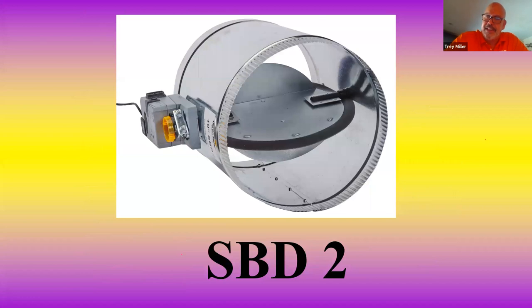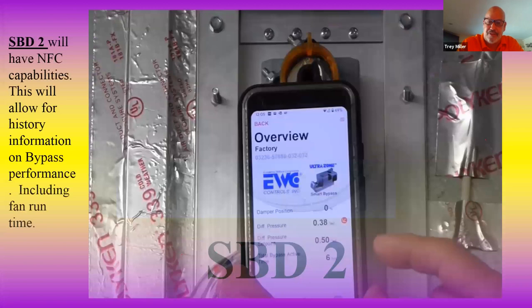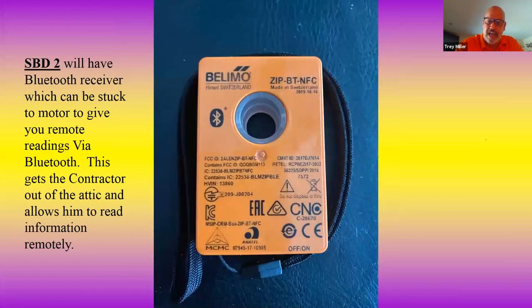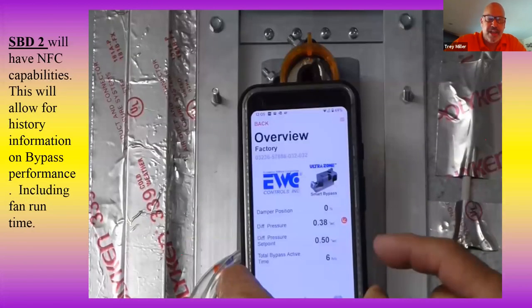Guys, this is exciting. John told me about this and I've been waiting, but the SBD2 is on its way. And let me show you what that is. First of all, you're going to have NFC, near field communication. The beauty of it there, guys, is you touch your phone to the motor, it's going to give you a readout, just like you see here, differential pressure, set point, total bypass active.